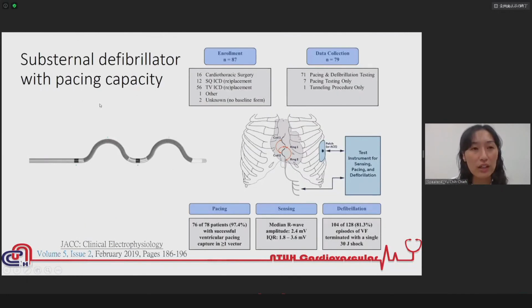Another small thing is the substernal defibrillator with pacing capacity. This is the design of the lead—it has two ring electrodes and two high voltage coils, and it is placed from the substernum to the retrosternal area. When it is connected to the patch, we can see the defibrillation success rate is very high.